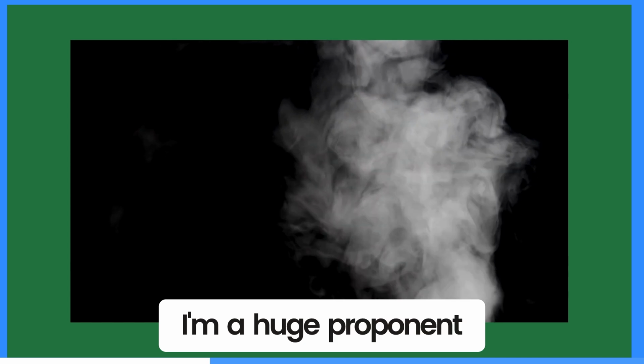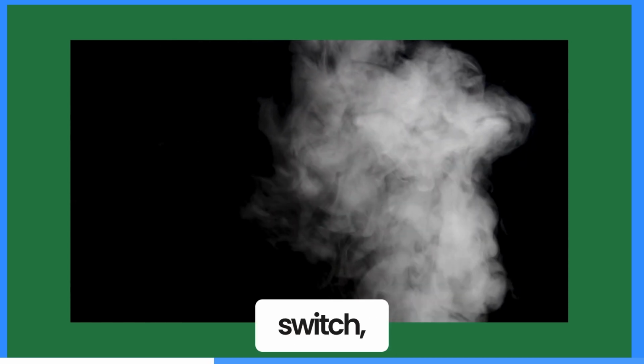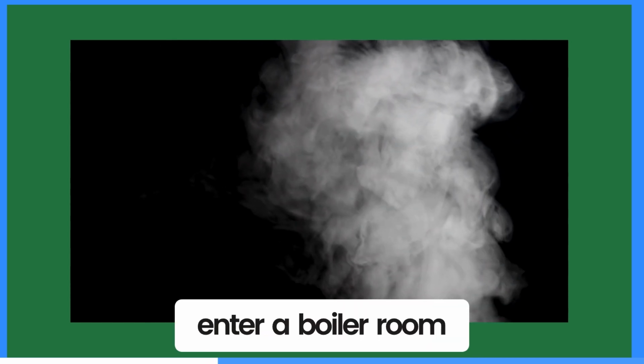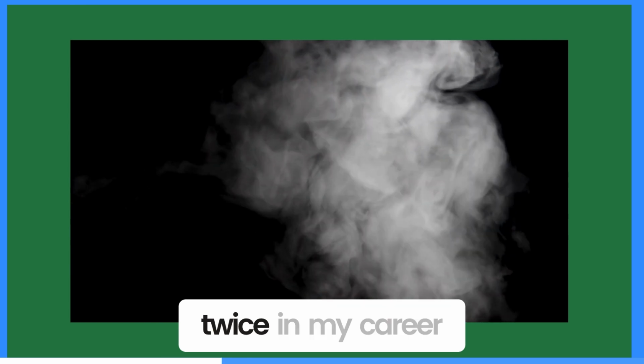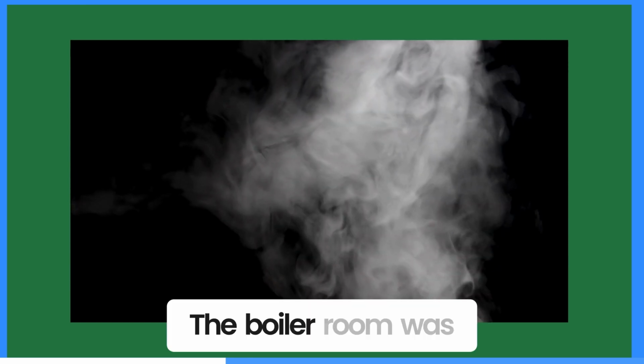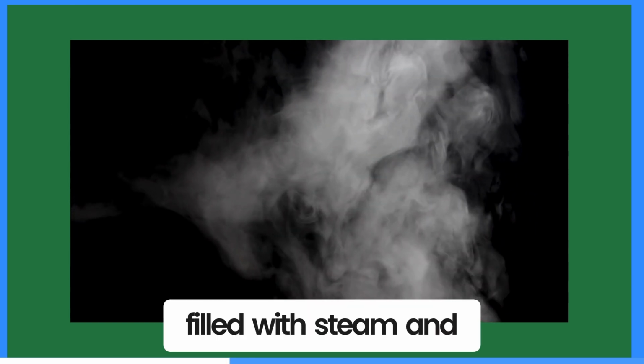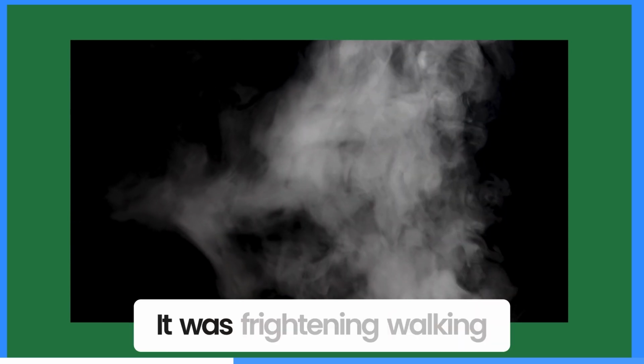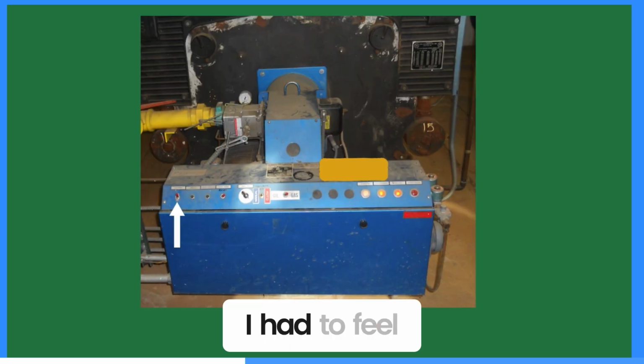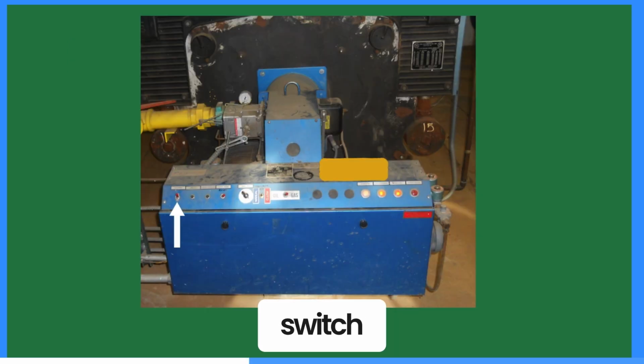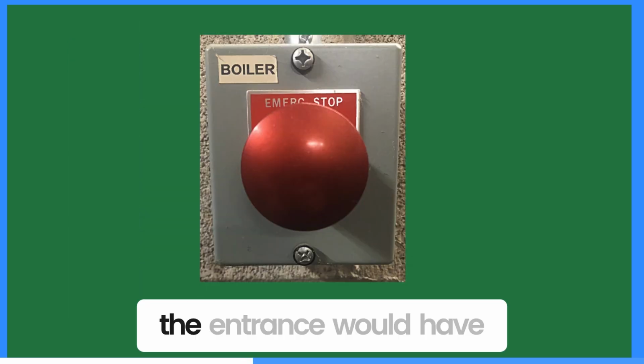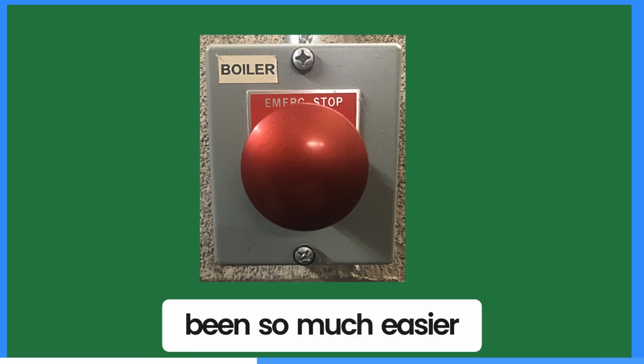I'm a huge proponent of the emergency door switch, as I've had to enter a boiler room with a runaway boiler twice in my career. The boiler room was filled with steam and had no visibility. It was frightening walking through the boiler room by sound only. Once in front of the boiler, I had to feel around for an on-off switch. A door switch at the entrance would have been so much easier.